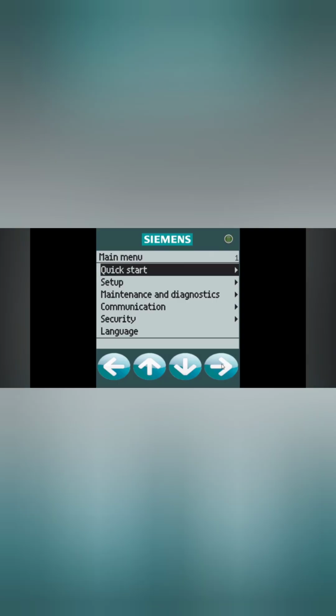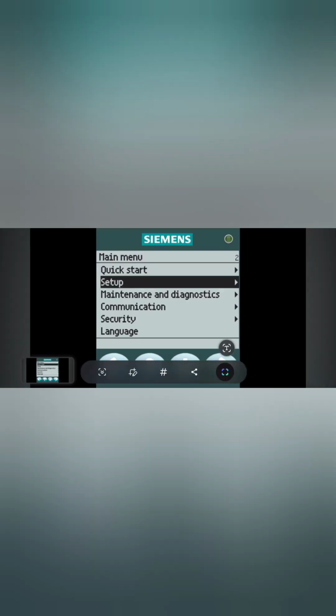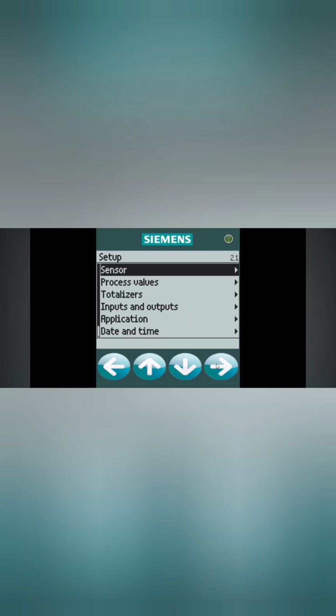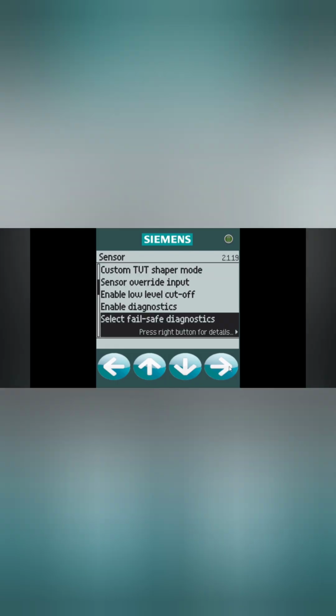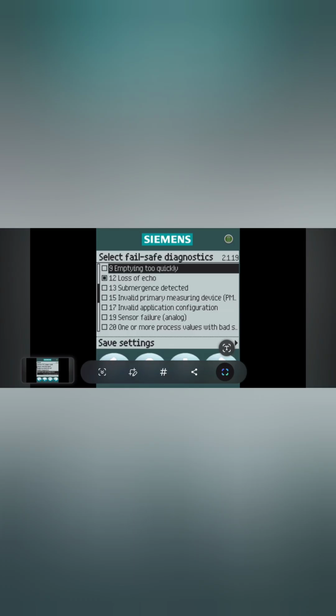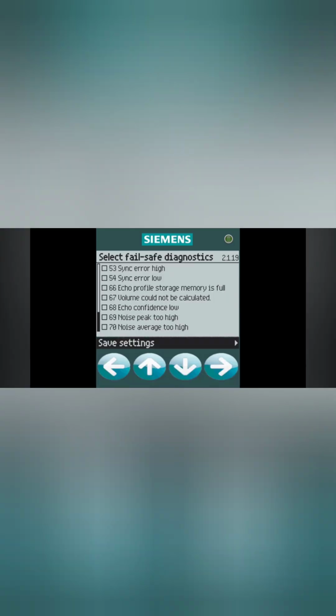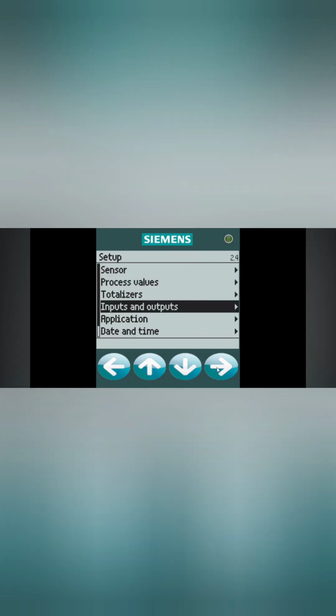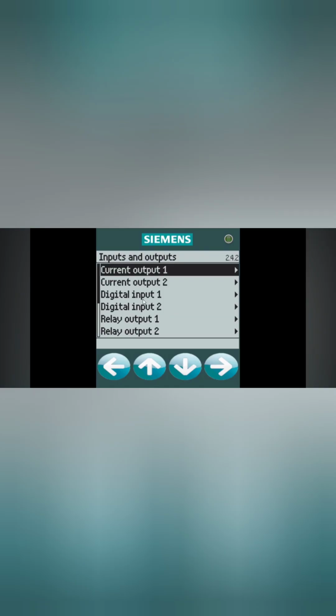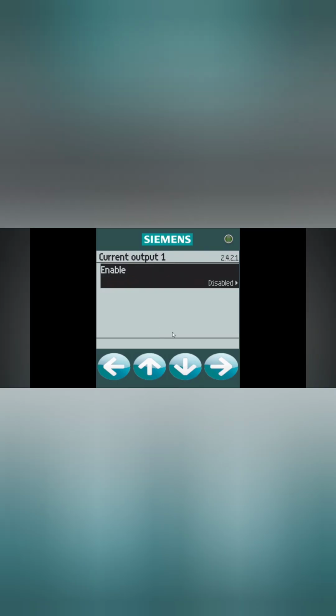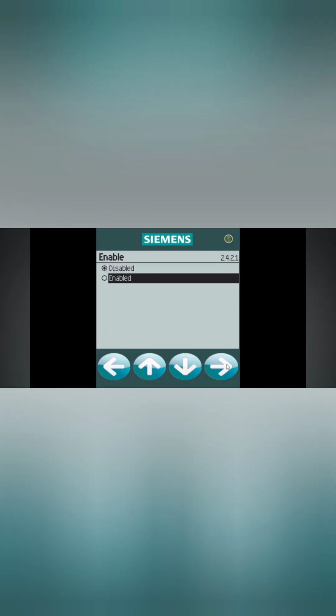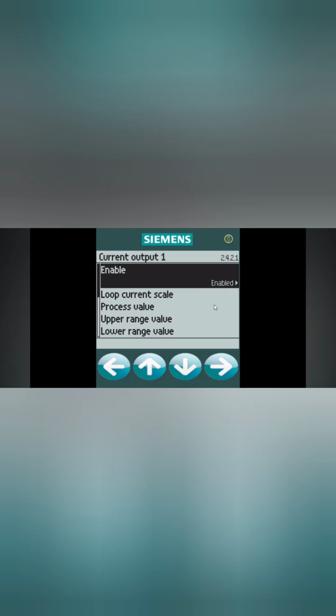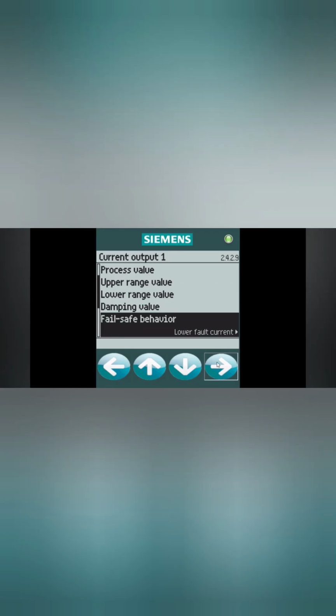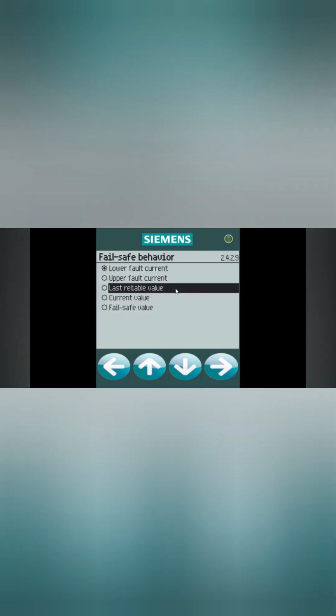Next I want to set up the failsafe behavior, so it's quick start, down to setup, sensor, then select failsafe diagnostics, highlight the loss of echo, and save the settings. From there we go back to setup, inputs and outputs, current output, and enable. Click on that and enable it. Now go back to failsafe behavior and choose high, lower, hold.